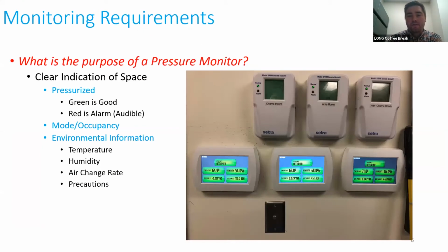The end user had this Setra system installed in their facility. You do see the green light there indicating that the room is at normal pressure. It does give you the pressure reading on that small screen. But when you put it side by side with the critical room controller, it's a night and day difference. You have your green thumbnails there that clearly indicate the room is occupied, if it's safe to enter.